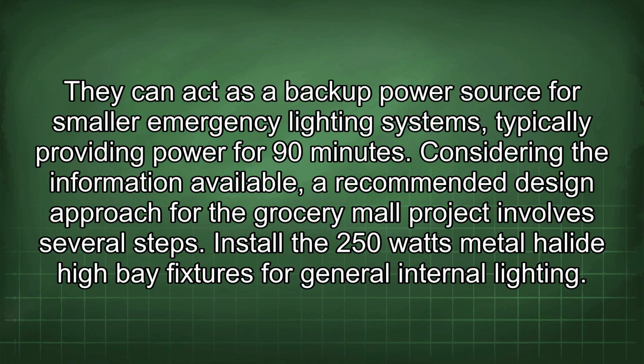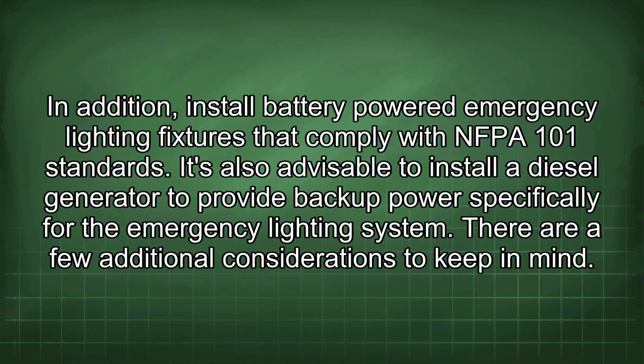Considering the information available, a recommended design approach for the grocery mall project involves several steps. Install the 250 watts metal halide high bay fixtures for general internal lighting. In addition, install battery-powered emergency lighting fixtures that comply with NFPA 101 standards. It's also advisable to install a diesel generator to provide backup power specifically for the emergency lighting system.